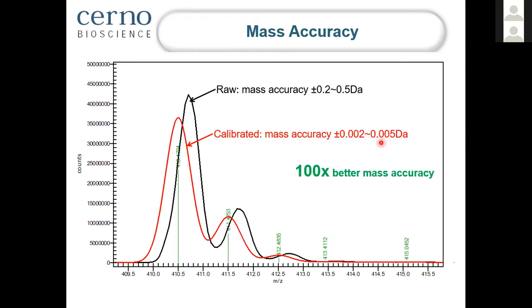And the reason we can achieve that, fundamentally, is because we calibrate the peak shape. Even though it's a unit mass resolution, the peak is still pretty wide, at 0.5 or 0.7 AMU. Because we know the peak shape, we can determine the peak position 100 times better. And that gives us 100 times more mass accuracy, which is remarkable when you think about it.